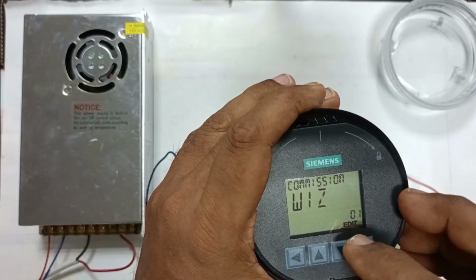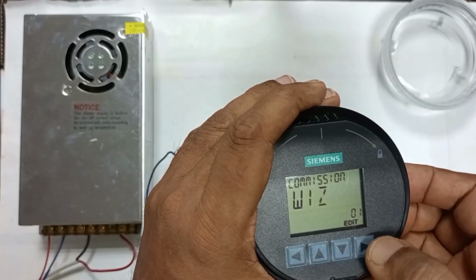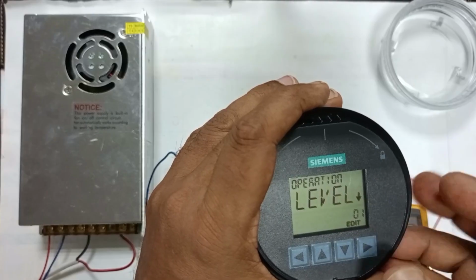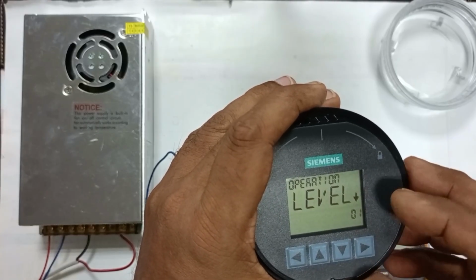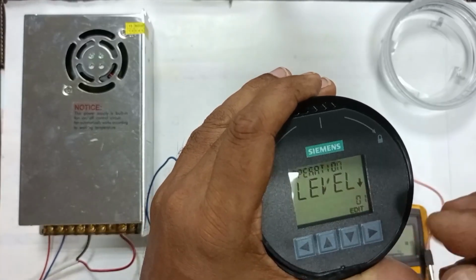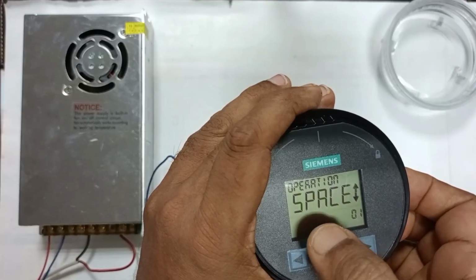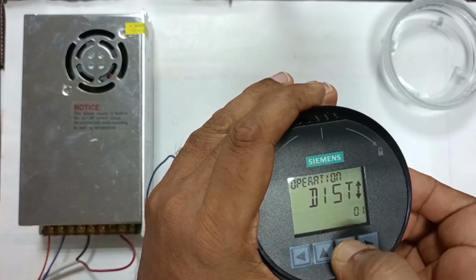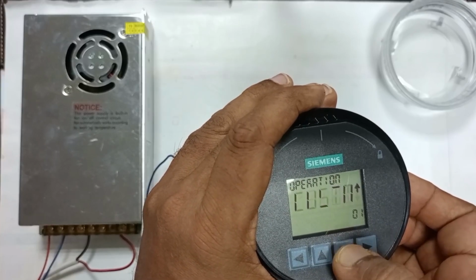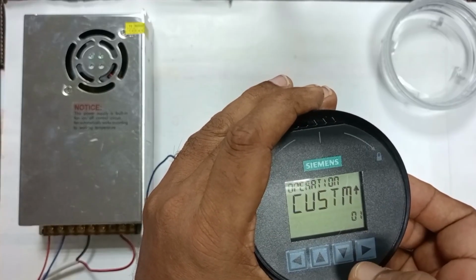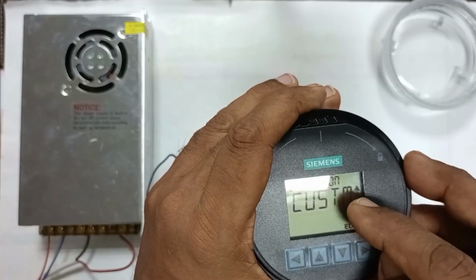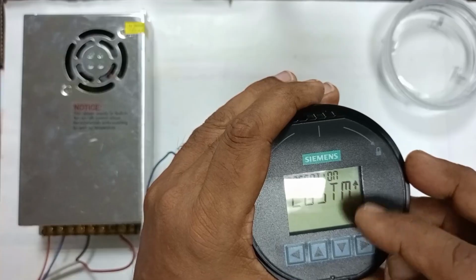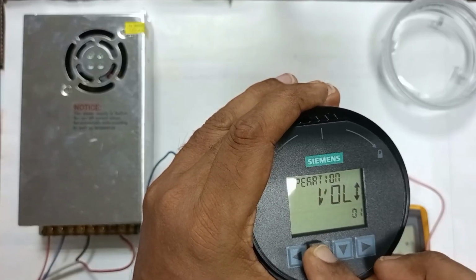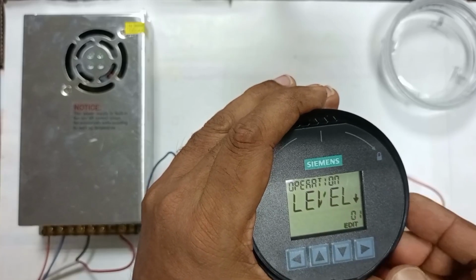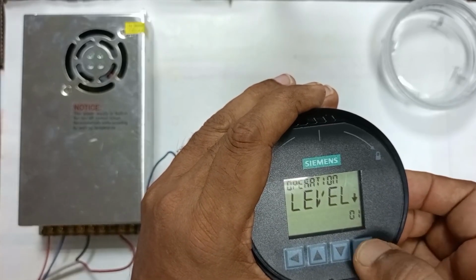For commissioning, here is, you see, this is the first one, and edit. If we press enter, then the commissioning level goes downward, that means different values. Here is operation, that means for which we will measure with this transmitter. Here is, you see, level, and also space, distance, volume, flow, and custom. That means you can set another thing. Here you see this upward arrow, that means there is no lower value. If we press upward, then again you can see flow, distance, space, level. As we will use this transmitter to measure level, we will press enter here.